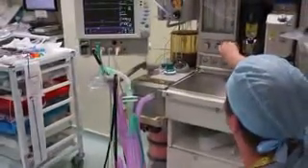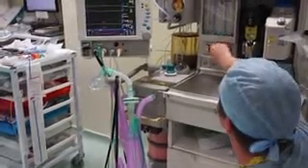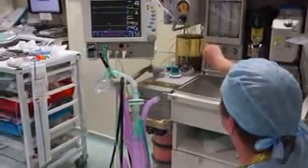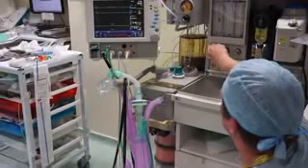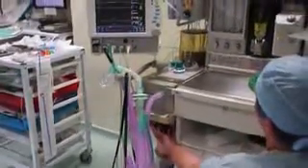I find the simplest way to do this is to use the common gas output. We're going to flick that open to use the auxiliary output. We're going to go through the flow meters in turn — we'll start with the air, go through the full range of the flow meter, then turn it off. Then the nitrous, checking the hypoxic guard, and then finally the oxygen. We'll drop that around to 6 liters for the rest of the test. We're going to briefly occlude it now, looking for the drop in the bobbin.